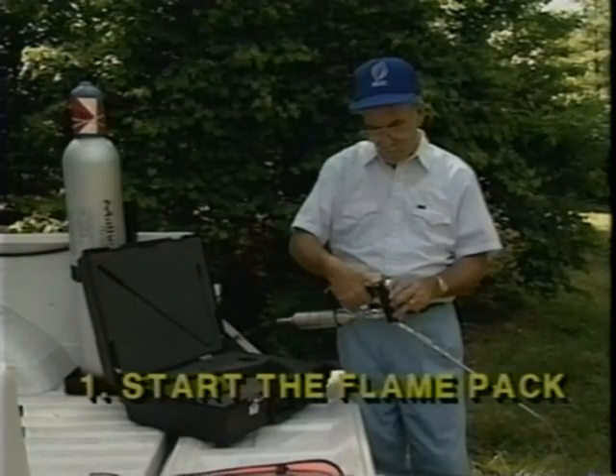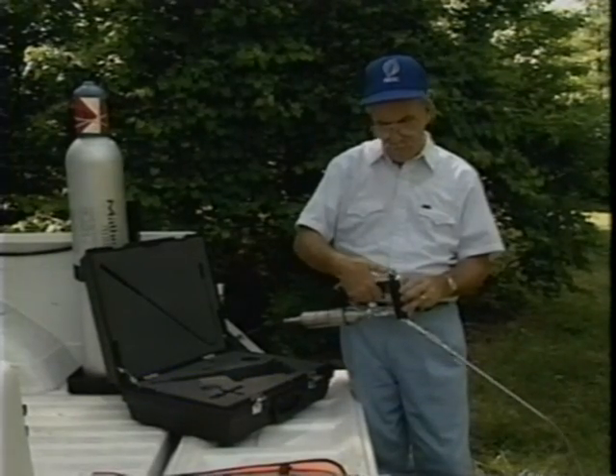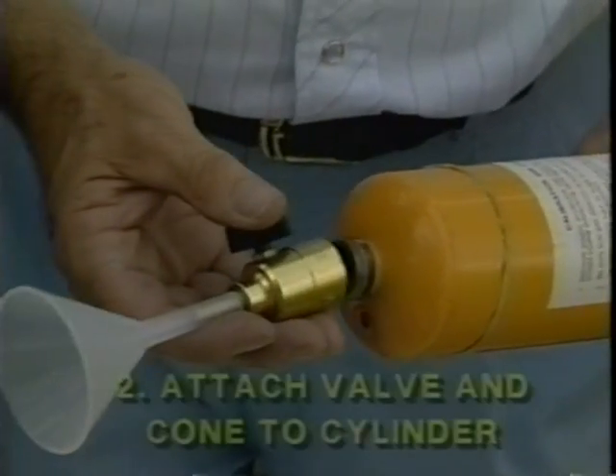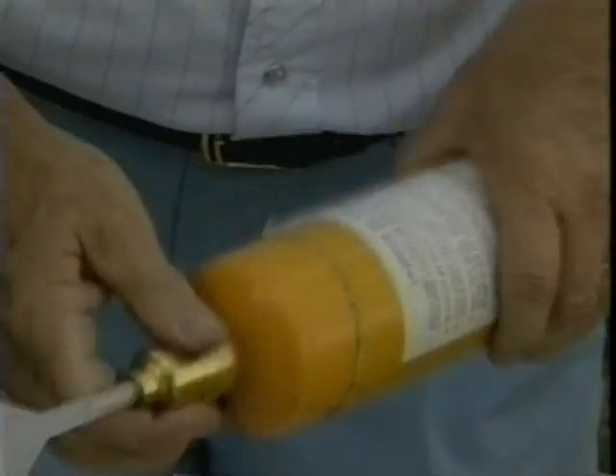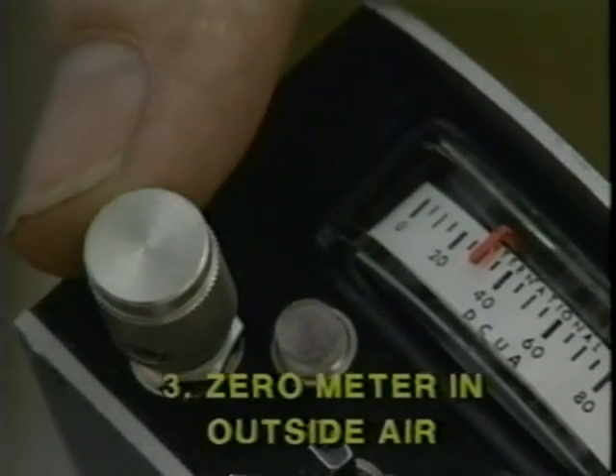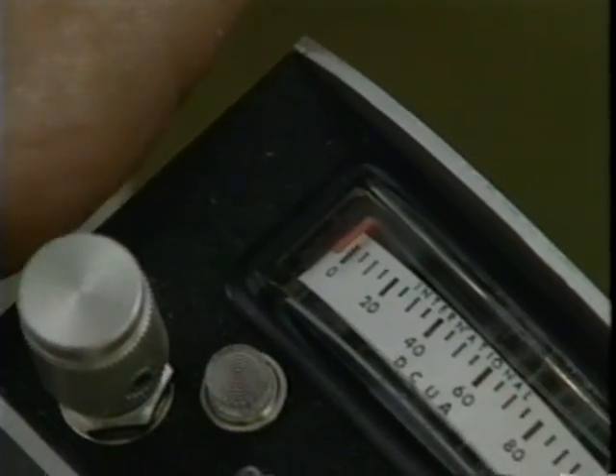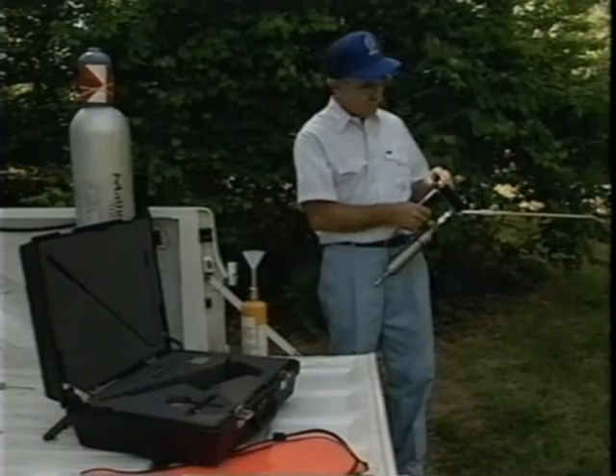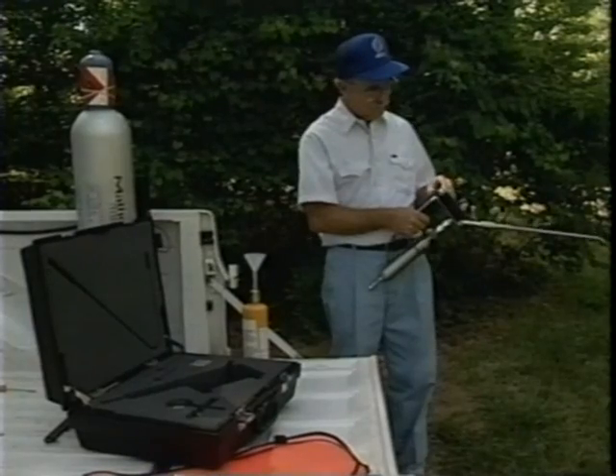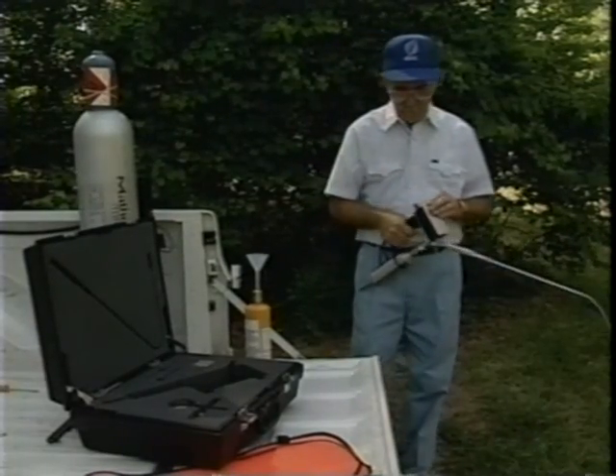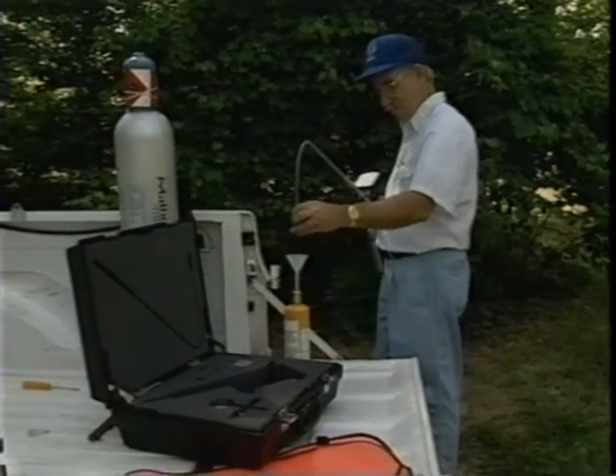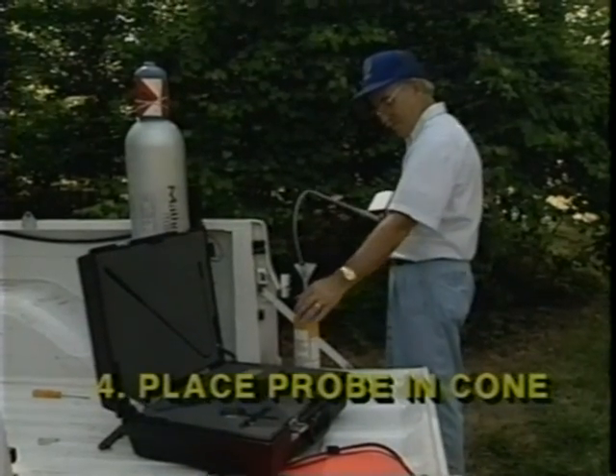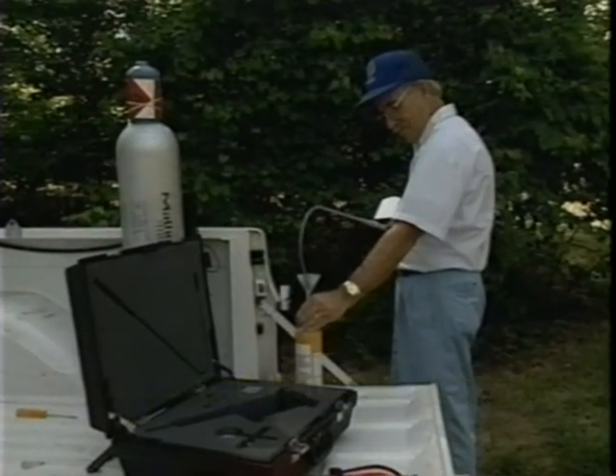1. Start the FlamePack 400 and allow ample warm-up time. 2. Attach valve and cone to 50 parts per million test cylinder. 3. Zero the meter in clean outside air. The surrounding hydrocarbon level must be relatively low in order to get a near full-scale reading using 50 parts per million test gas. 4. Place the probe intake into the cone.